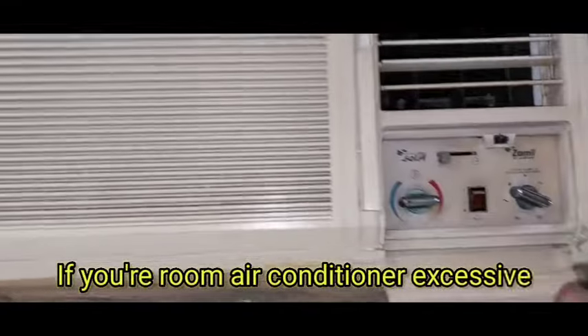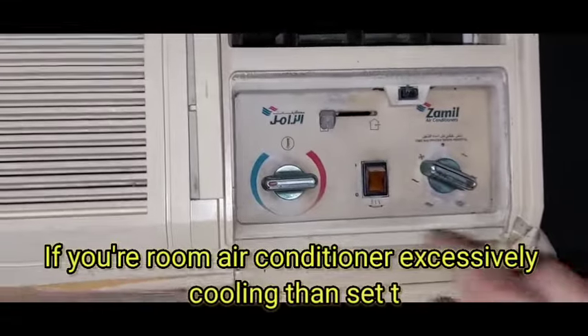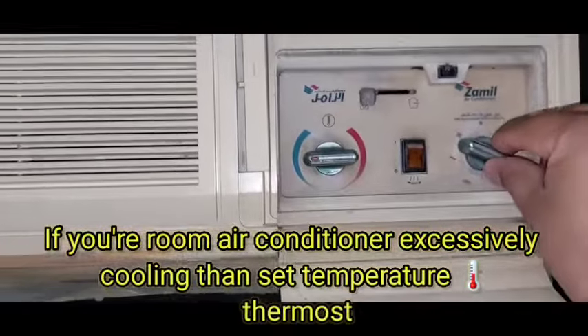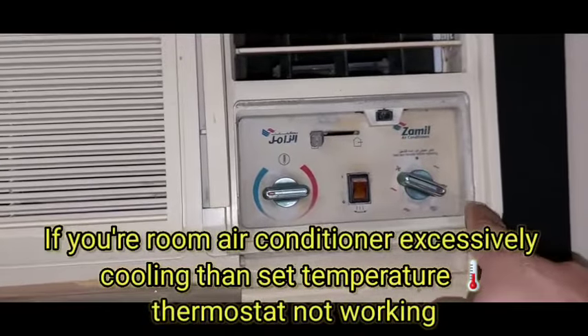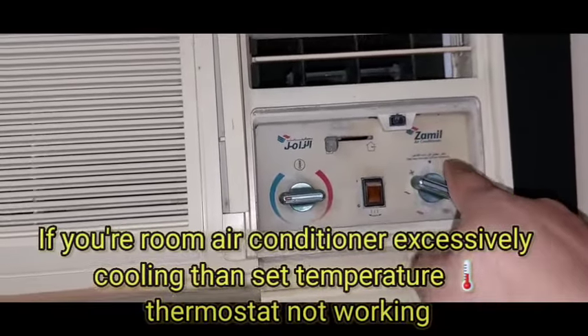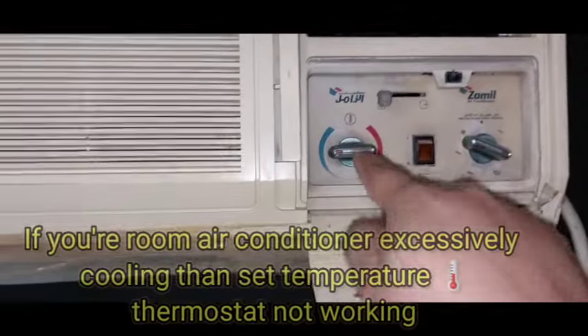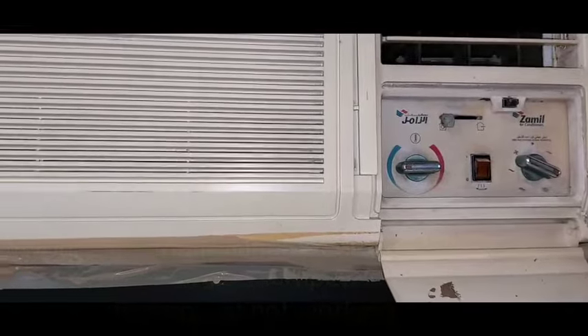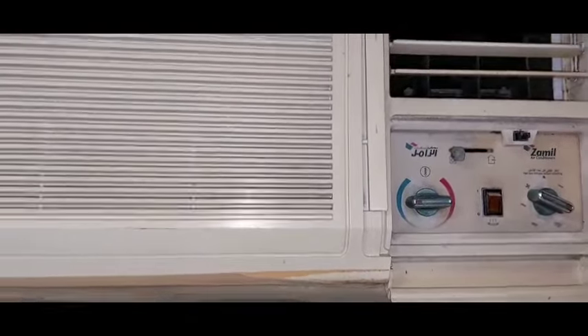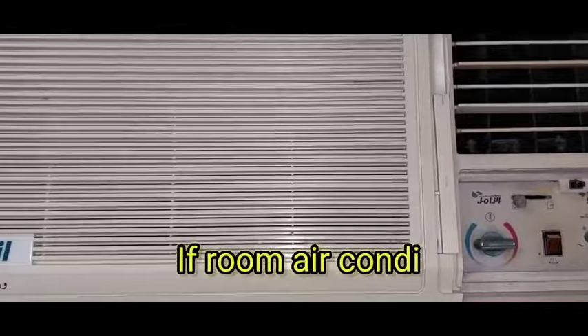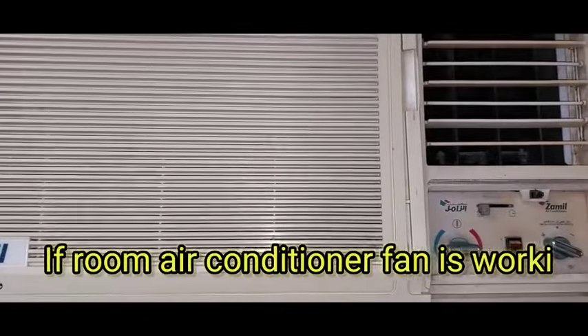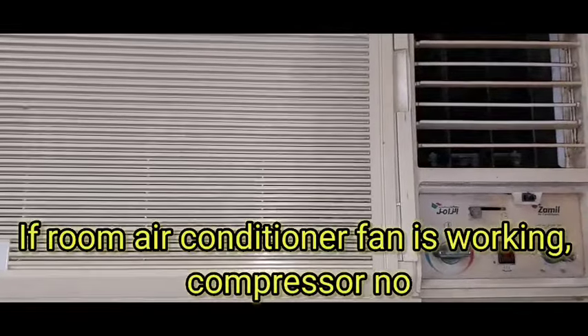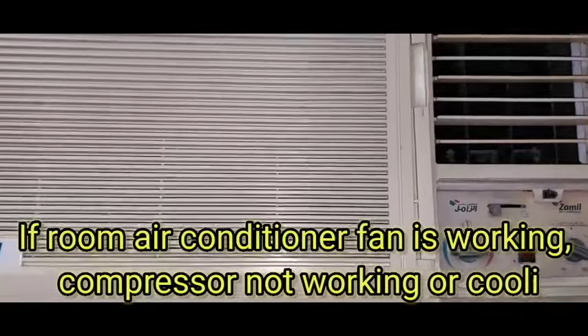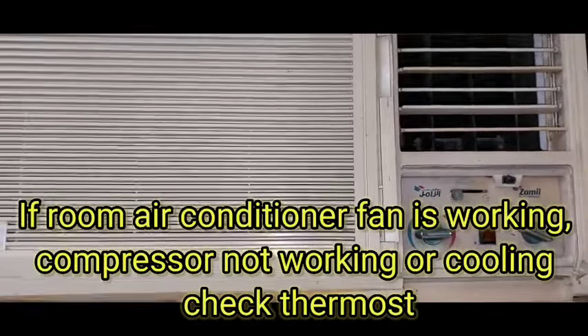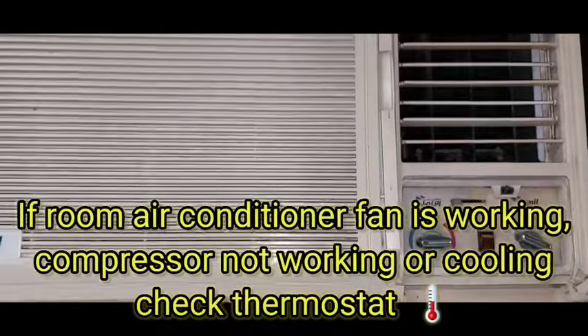So you can see the control board. I set it in between, and the fan is at medium speed, so it is low, medium and high. The temperature is set in between, around 22 to 23. At this temperature the compressor should turn off. So I kept a timer and watched for 3 hours. There is no tripping, and the compressor is not shutting off, so there is a problem with the thermostat.